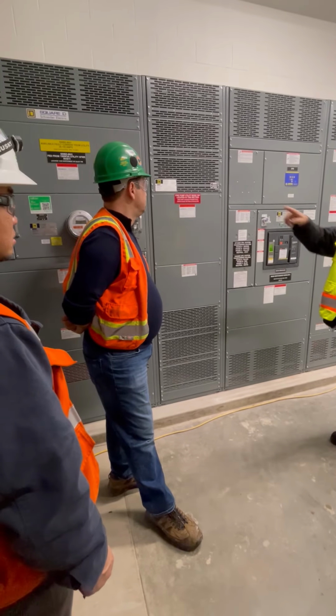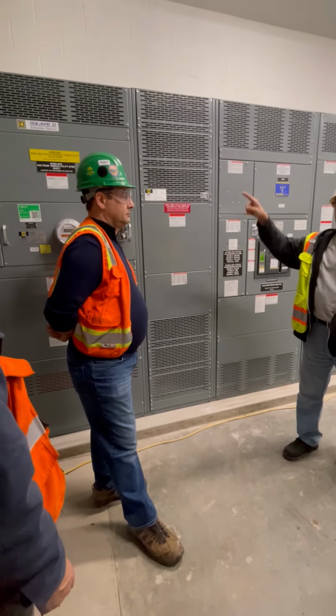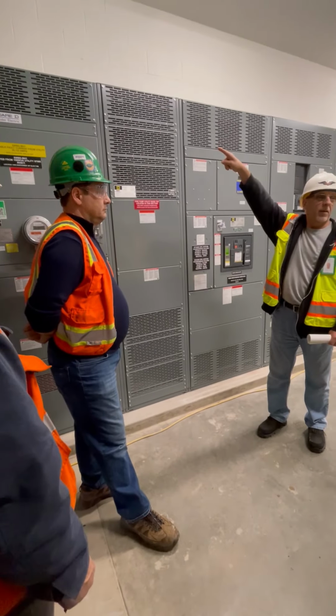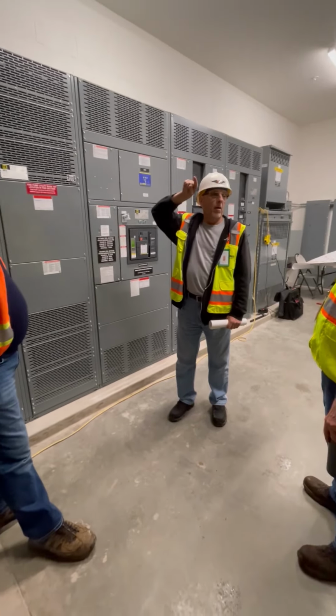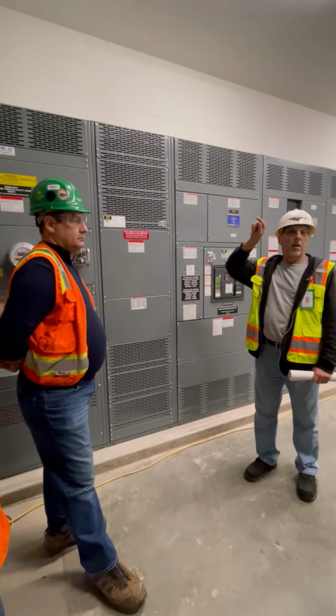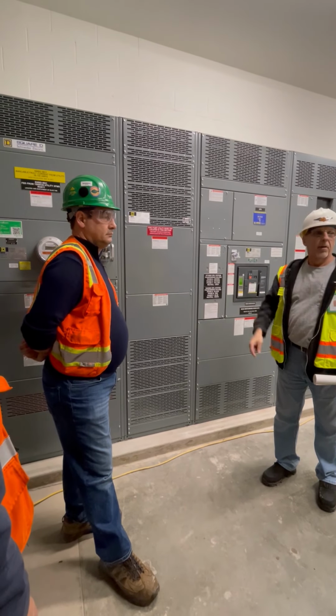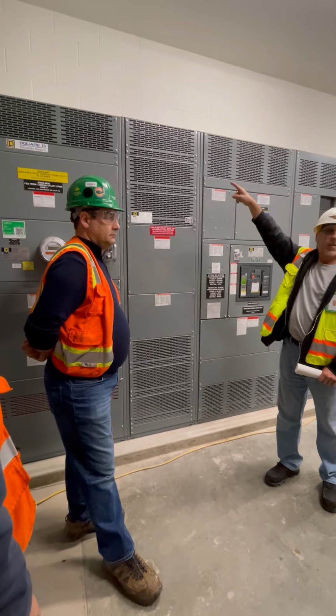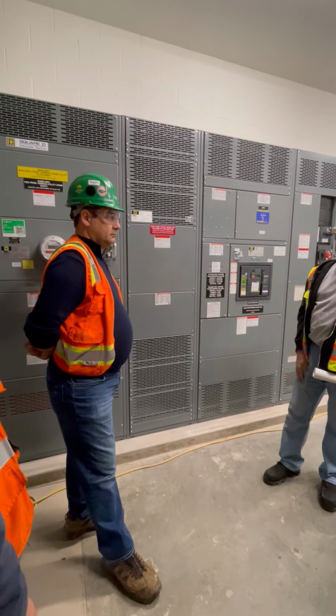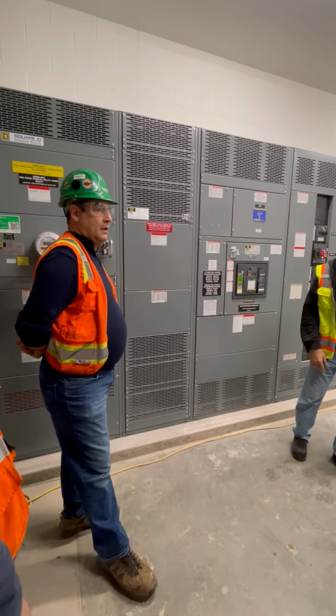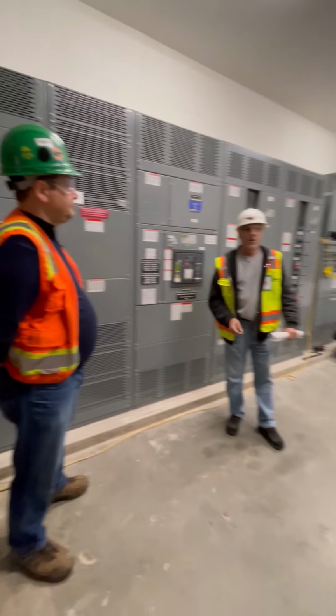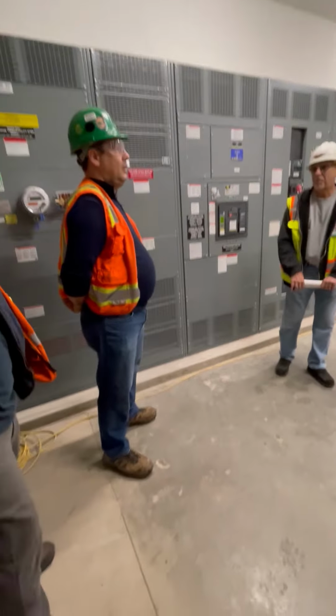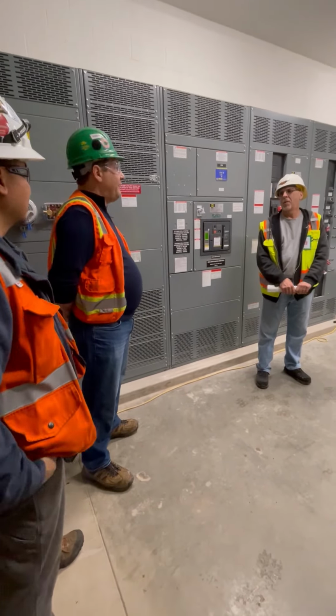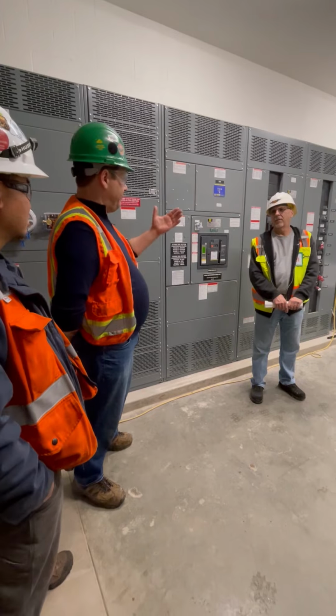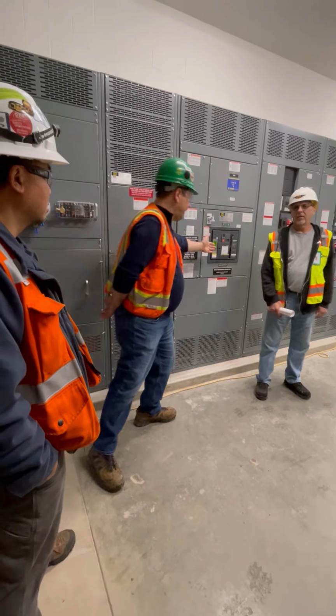Basically, like I said, it comes right from the street. You would have to kill it out there. It doesn't have a disconnect for maintenance at the fire pump itself? There might be a shut off there, but you can't kill the power to it unless you disconnect it at the utility's box. It doesn't have one. It runs until the building burns down, or the pump burns down. In case of a fire, fire can create faults that can trip a breaker.